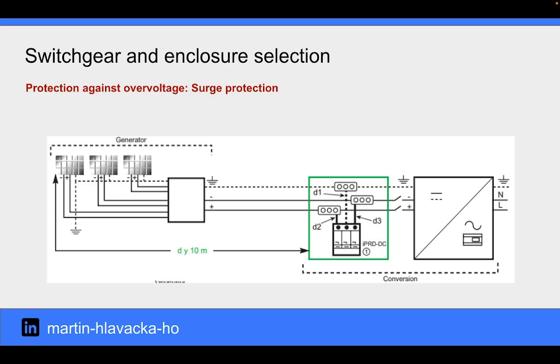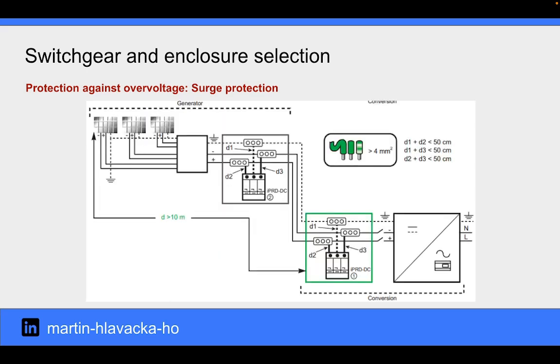On this slide, you can see an example of PV system where only one SPD is installed on the DC side due to the distance between the conversion part and the generator part that is less than 10 meters. On this slide, you can see an example of the PV system where two SPDs are installed on the DC side due to the distance between the conversion part and the generator part that is greater than 10 meters.